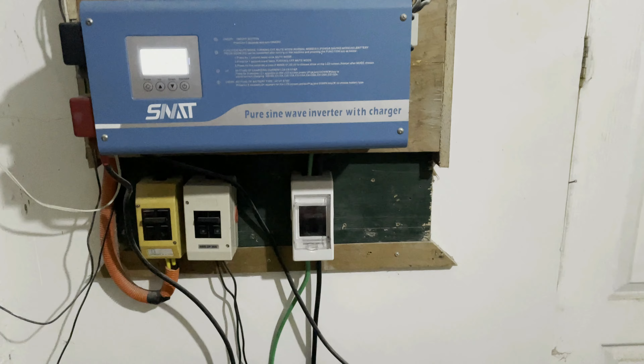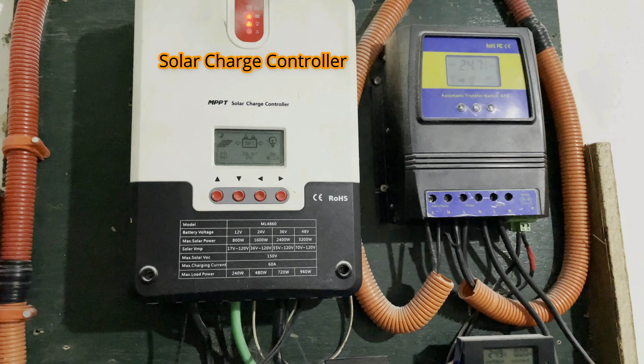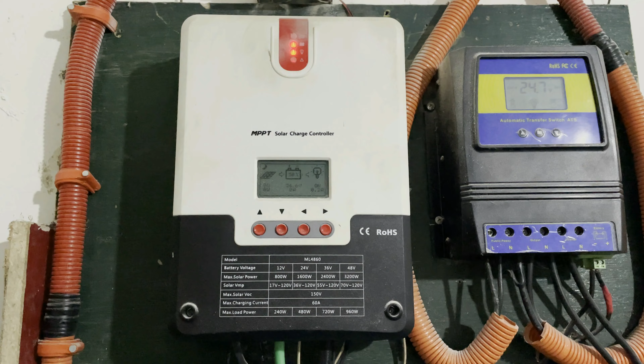The main function of this device is to regulate the power coming in from the solar panels to the battery to maximize its efficiency. It has an undervoltage as well as an overvoltage mechanism that protects the battery from wearing out too easily. It has 3 charging stages. Stage 1 is called the bulk or fast charging, when the battery is below 80%. The second stage is referred to as the absorption stage, when the remaining capacity before it gets full is only 20% or less.